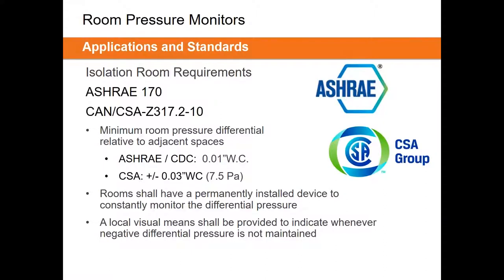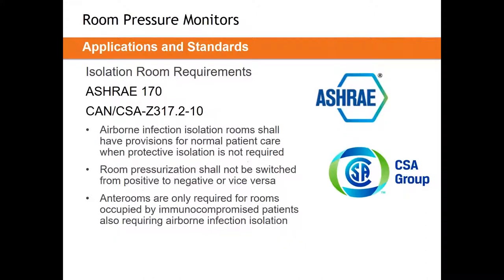Generally speaking, those room pressure monitors should provide a local visual means to indicate whether you have negative or positive differential pressure, and ideally will also show the magnitude of that pressure.